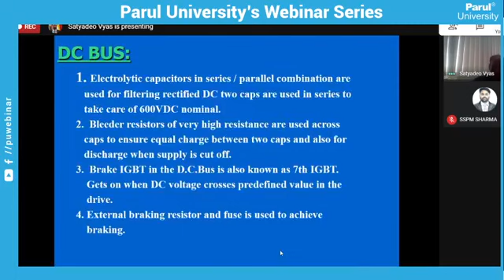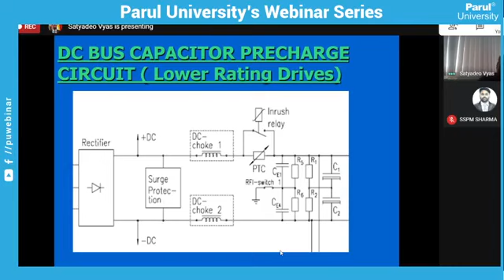One more feature is the DC bus capacitor pre-charge circuit. A large rating electrolytic capacitor is used for filtering purposes. In that condition, what will happen? If we switch on the rectifier, this capacitor will draw very large current, because when you charge any capacitor, it draws very high inrush current. To limit it, some choke or resistance is used in series, and after some time, that is bypassed. This is the pre-charging of the capacitor.